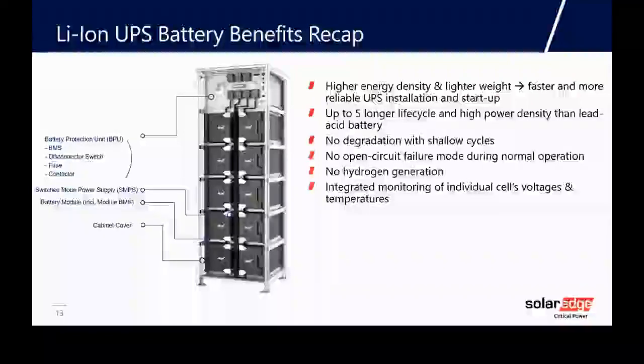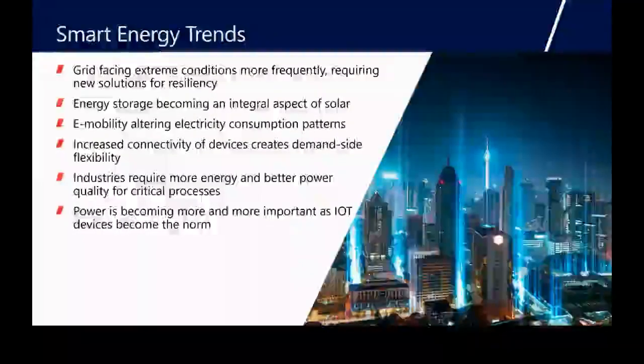So just to recap on lithium: much higher energy density, up to 5 times longer cycle life—actually it's 10 times longer in most applications now, that needs to be updated. No degradation with shallow cycles. When it does fail, it doesn't fail open circuit like VRLA, so you still have a circuit, which is very good. No hydrogen to deal with, and you get all this battery monitoring as standard.